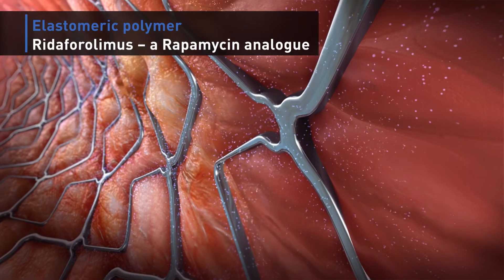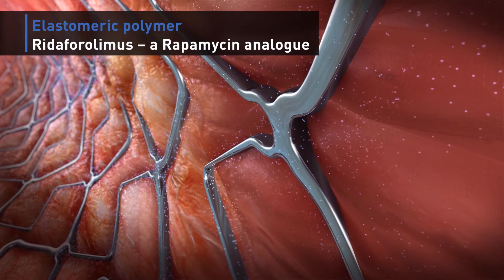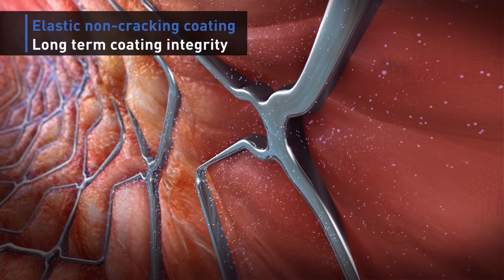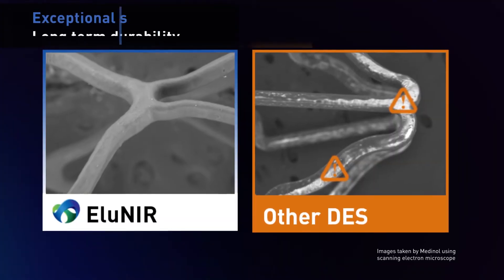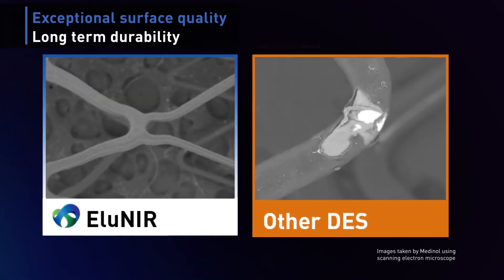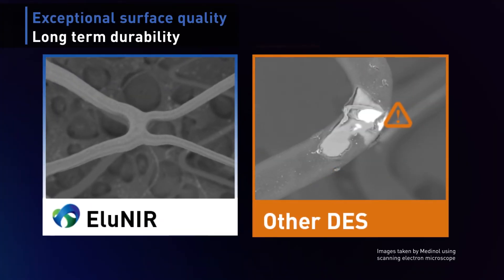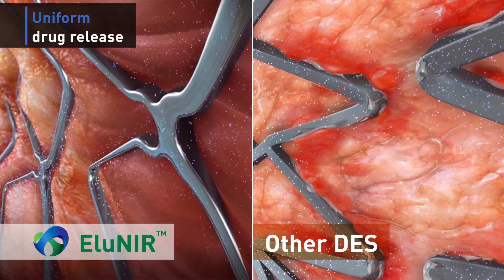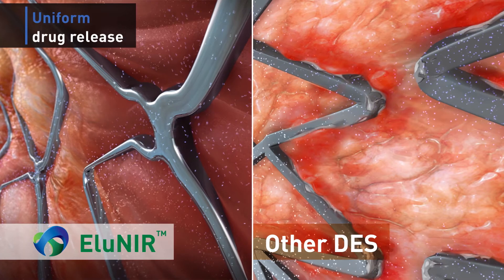EluNIR is coated with a unique formulation of an elastomer and Ridaforolimus, which is a rapamycin analog. The elastomeric coating ensures an elastic, non-cracking coating with long-term integrity. Many stents have a brittle coating that may crack, peel, or flake. Such surface defects may lead to non-uniform drug release and were associated with inflammatory processes.